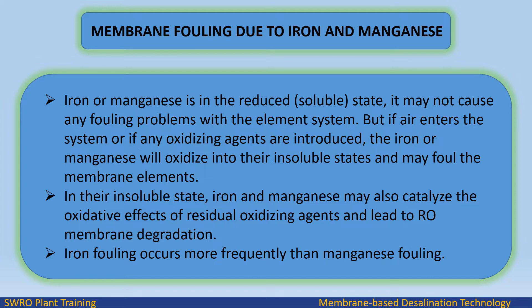If iron or manganese is in the reduced, soluble state, it may not cause any fouling problems. But if air enters the system or any oxidizing agents are introduced, the iron or manganese will oxidize into their insoluble states and may foul the membrane elements. In their insoluble state, iron and manganese may also catalyze the oxidative effects of residual oxidizing agents and lead to RO membrane degradation. Iron fouling occurs more frequently than manganese fouling.